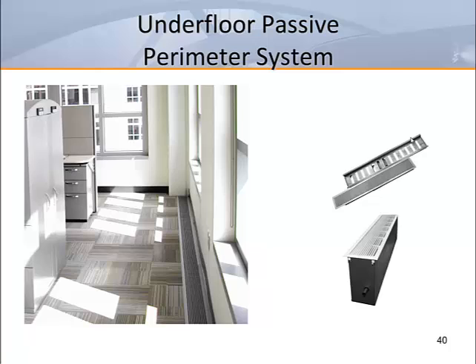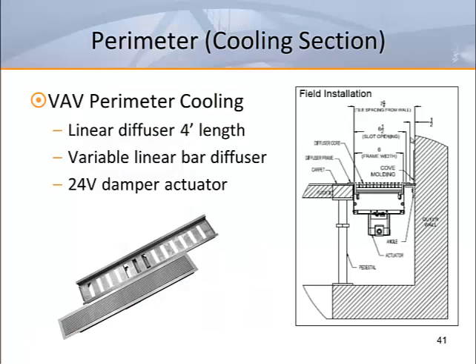The passive perimeter system consists of a perimeter hot water heating section or a perimeter SCR electric heating section, and the perimeter variable air volume cooling section. This system uses a continuous run of linear bar grill that gives the system an architecturally appealing appearance along the perimeter. The system is modular so that heating or cooling units can be placed as required to match climate and zone load conditions. First, the VAV perimeter cooling system.